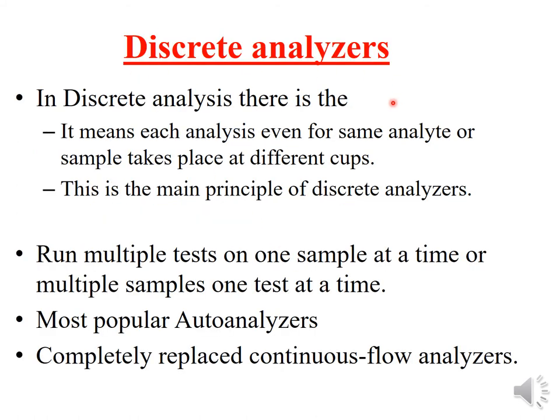In discrete analyzers, the analysis for the same analyte or sample takes place at different cups — meaning each analysis, even for the same analyte, takes place at different cups. This is the main principle of discrete analysis.